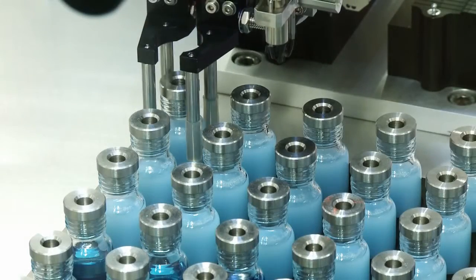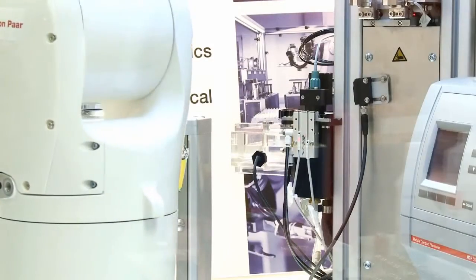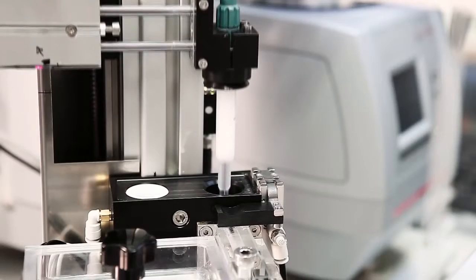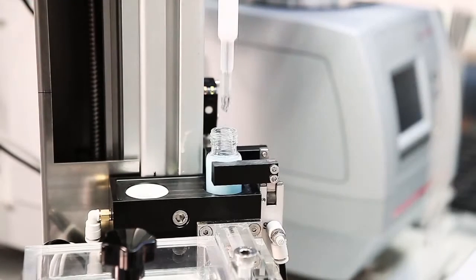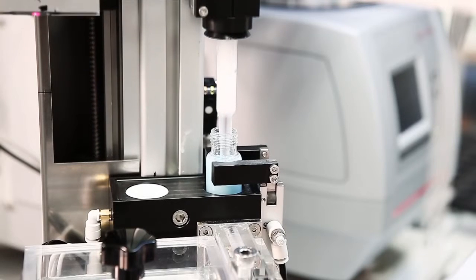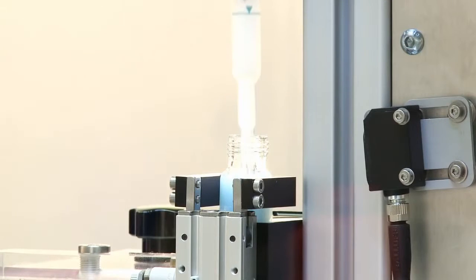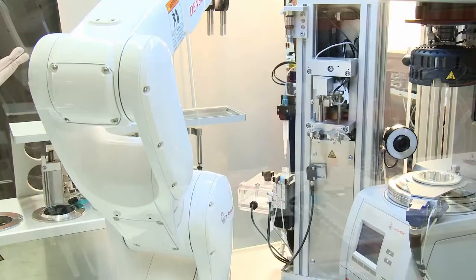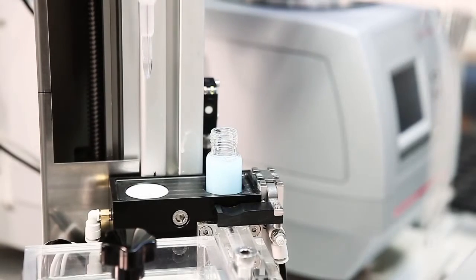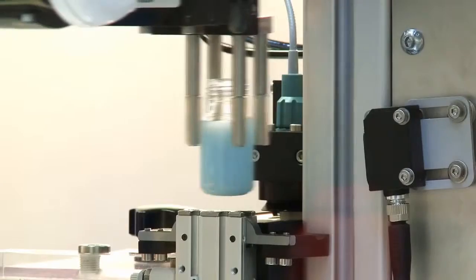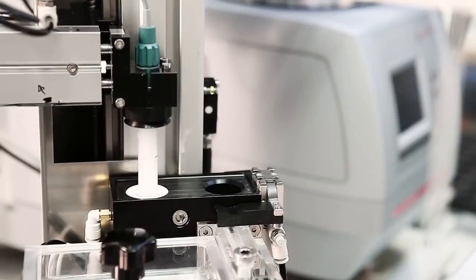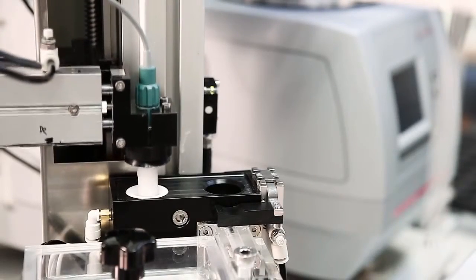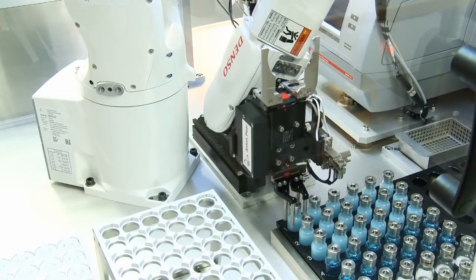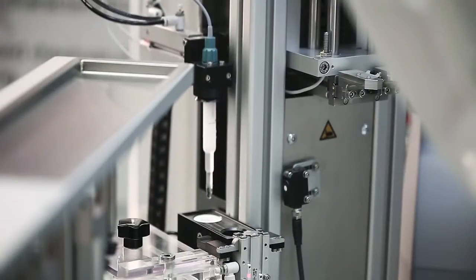pH is one control parameter which tells you whether your sample is as required. This pH module enables the detection of pH alongside or in addition to analytical determinations from exactly the same sample. It is equipped with an automatic cleaning routine, a 3-point calibration and a resting position. The entire operation from getting the sample up to measuring the pH of the sample is fully automated.